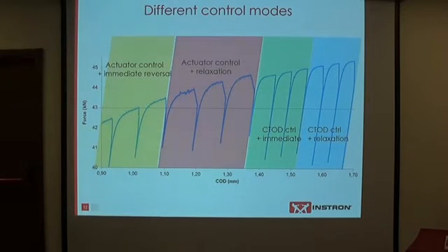And then, just to show you that it's quite doable, we've offered this within our software for a number of years, but very few people use it, which is to control off the COD gauge itself. And here we actually get a much nicer control of the system. We load up, and then we turn around, go straight back down, and it's open to debate, but it seems like that separation there is a bit narrow. But it's a very neat control. And you can see then if we deliberately introduce a relaxation there, we're still holding at the same COD.